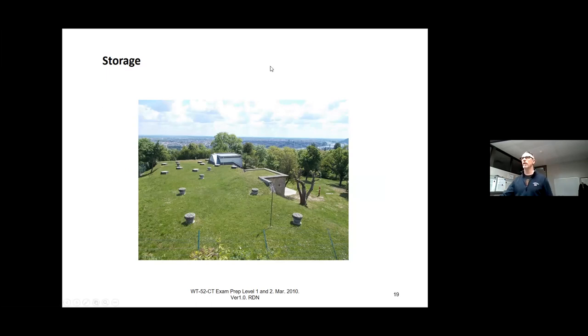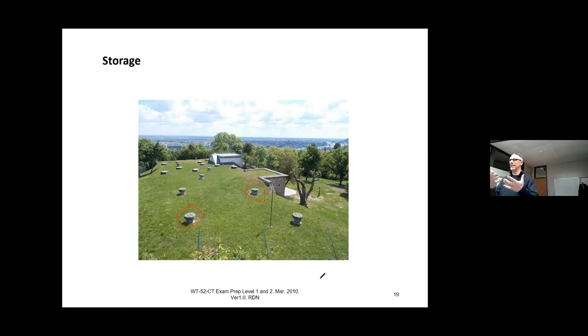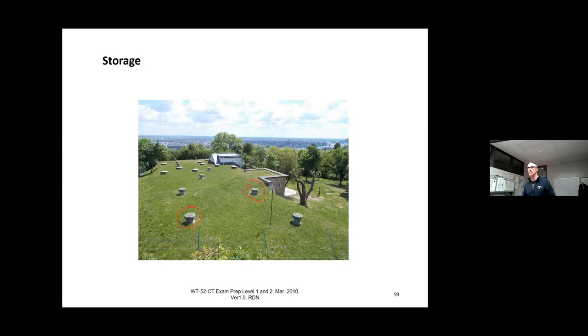As an operator it's very important to inspect these so they're sealed. They should let air in but have screening so mice or animals don't get inside and contaminate your reservoir — and to keep people from putting stuff in there. Make sure security is good. Your entrance hatches need to be locked and checked often to make sure nothing has been tampered with.